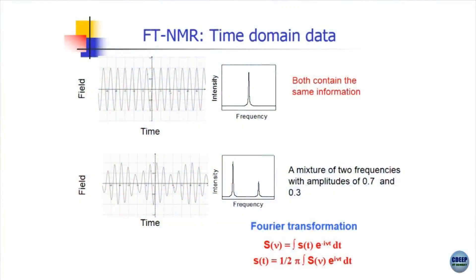What we will try to learn is how FTNMR works. In FTNMR you record the data in the time domain. If it is monochromatic radiation you get a sine wave or cosine wave; if it is polychromatic radiation you get a beating pattern — an interferogram. Then using Fourier transformation you can switch from time domain to frequency domain with no trouble at all; in fact it happens at the click of a mouse.